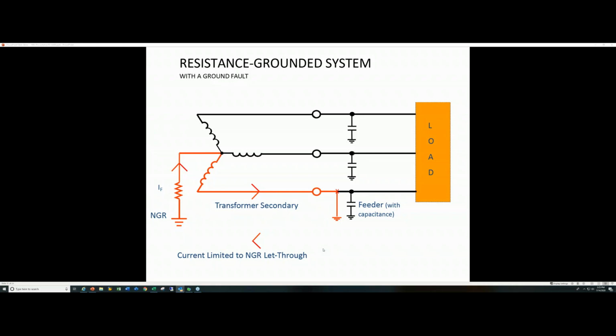And with such a low fault current, you can stay running. Now, there's the magic in it, and we can talk about that later. I'll let Serge tell you about that if it comes up. But you can have a faulted phase on a three-phase 480-volt motor, and the motor continues to run. It's really interesting, and it has helped us. We are a 24/7 facility, 7 days a week, and every hour of downtime on our machines correlates to $30,000 an hour, so it's pretty significant.